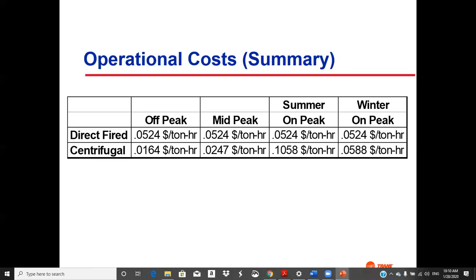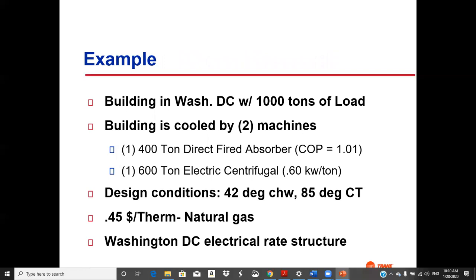But anyway, you see, we've got a pretty good deal going on here. It's just a question, will that amount of savings be enough to justify the investment in the equipment? Okay, so let's look at some details on our example. Building in Washington, D.C. with 1,000 tons of load, cooled by 2 machines. One 400-ton direct-fired absorber, COP 1.01, and a 600-ton electric centrifugal at 0.6 kW per ton.